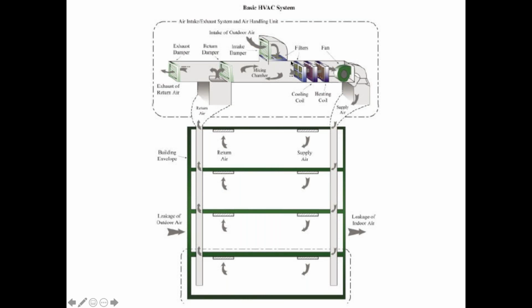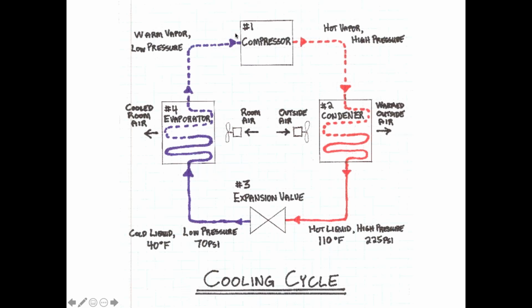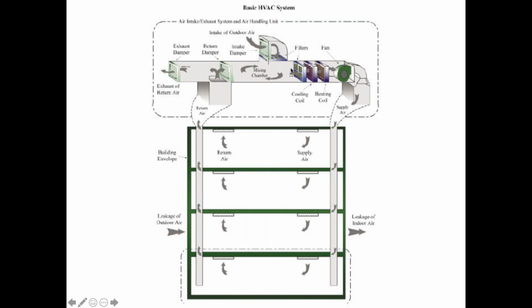So here this is shown as these coils in the ductwork. And in addition to that, you'll notice the return air that's coming from the ceilings. It's coming up in the ceiling and returning to this unit, right? Well, there's a return air damper, and there's a fresh air intake here as well. So this air that's returning and going back to the fan, we can open and close louvers, which look kind of like Venetian blinds, opening and closing. We can open and close louvers so we can control how much air comes back and how much is spilled out of the building. In other words, only a certain percentage of it comes back and is reused and is replaced instead by fresh air, right? So what comes back to these coils is a mixture of fresh air and return air.